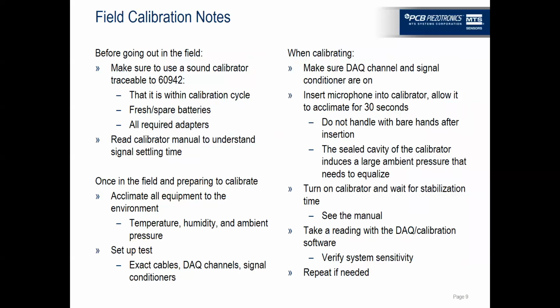And the next step is insert the microphone into the calibrator and allow it to get used to being under pressure in the calibrator for 30 seconds. Don't handle the microphone with bare hands because the temperature of your hands will have an effect on the microphone output. And the sealed cavity of the calibrator induces an ambient pressure change that needs to equalize around the microphone.